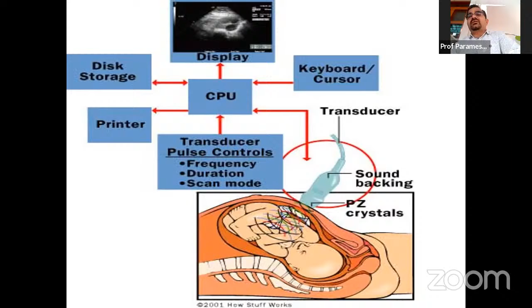Producing a sound wave is typically done by piezoelectric transducers, and the piezoelectric transducers are encased in a probe. The strong, short electrical pulses from the ultrasound machine make the transducers ring at the desired frequency. The frequencies can be anywhere between 2 to 18 megahertz. The sound is focused either by the shape of the transducer, a lens in front of the transducer, or a complex set of control pulses from the ultrasound scanner machine, which is called beam forming. This focusing produces an arc-shaped sound wave from the face of the transducer. The wave travels into the body and comes into focus at a desired depth.